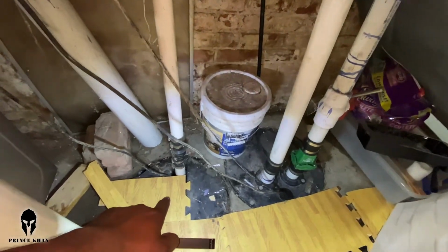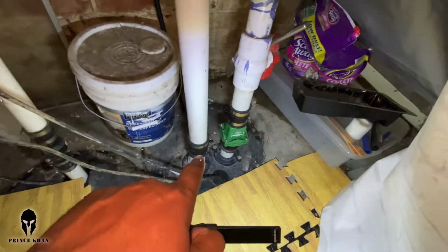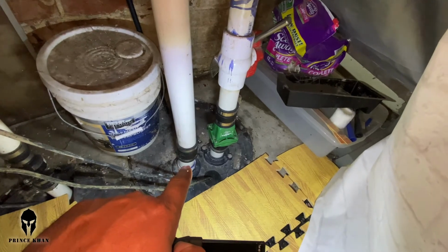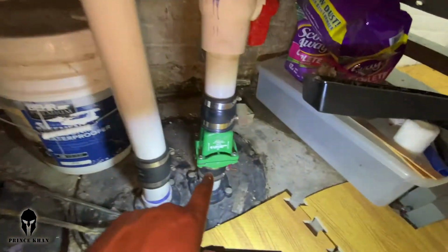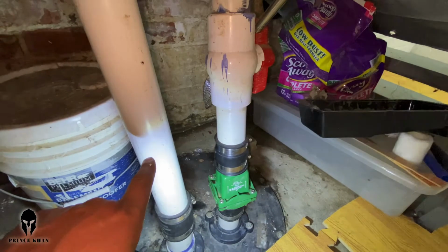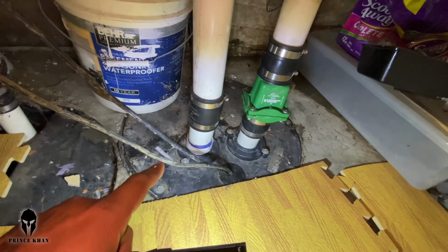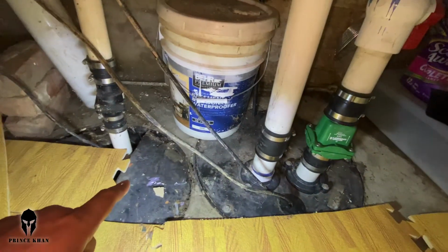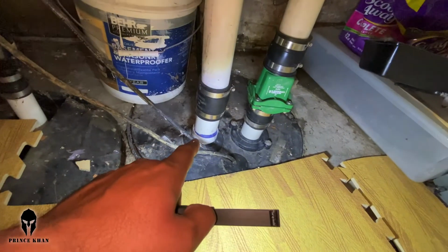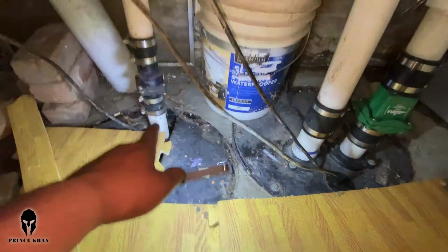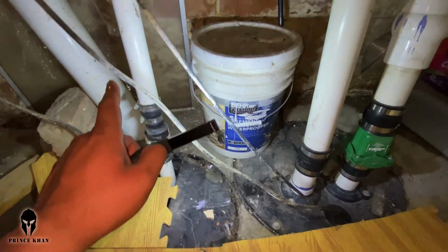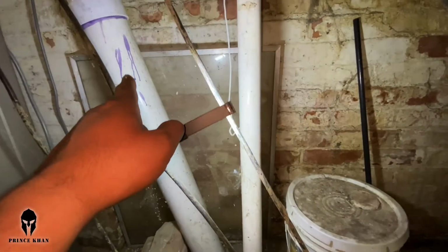This is a sump pump right here. Underneath here is the ejector pump. So as you can see, there's a one-way valve here, one-way valve here. This is where the air comes in, so it doesn't create a vacuum because this is a sealed container. And for some reason, if this one doesn't work, the water will come out here, go into the sump pump, and it will pump out to the same drain line. And the drain line is there.